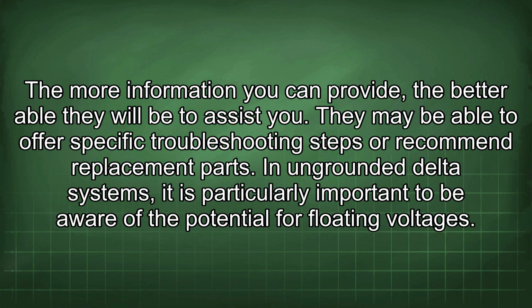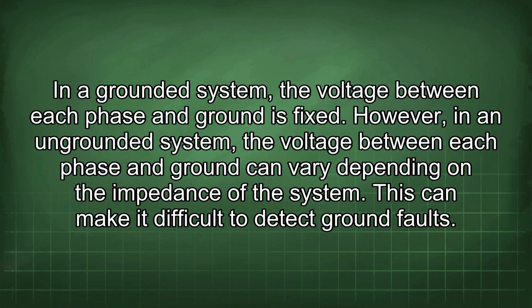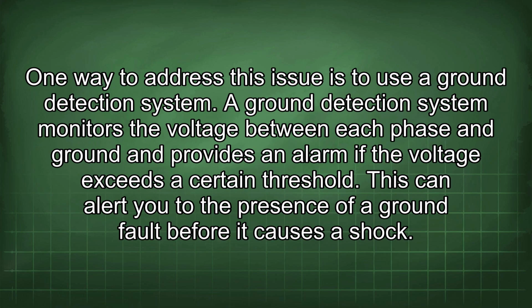In ungrounded delta systems, it is particularly important to be aware of the potential for floating voltages. In a grounded system, the voltage between each phase and ground is fixed. However, in an ungrounded system, the voltage between each phase and ground can vary depending on the impedance of the system. This can make it difficult to detect ground faults. One way to address this issue is to use a ground detection system.